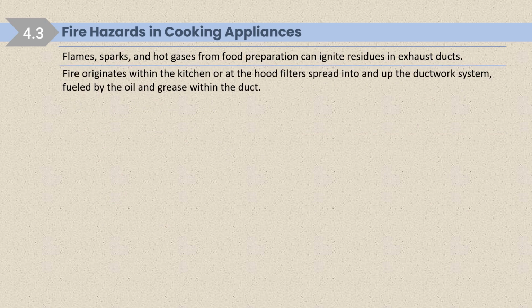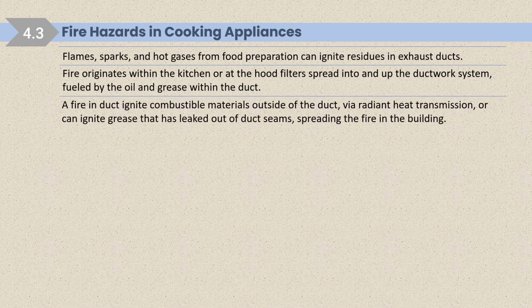Fire originates within the kitchen. It is not caused by the cooking equipment, but originates somewhere else in the kitchen or at the hood filter, and spreads into and up the ductwork system, fueled by the oil and grease within the duct. Initially it originated from somewhere else, and then it caught fire in the hood filters and spread into and up the ductwork system. A fire in the duct can ignite combustible materials outside of the duct.